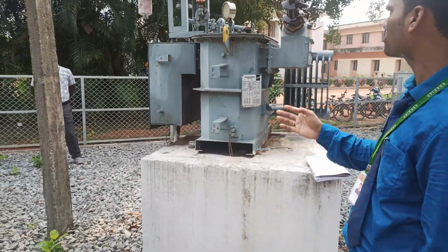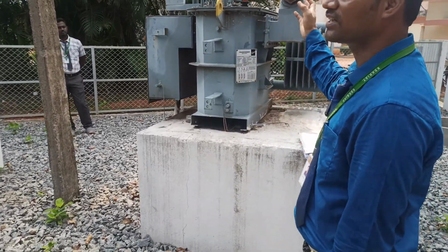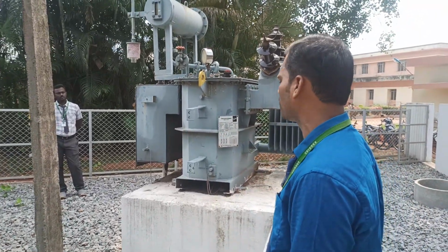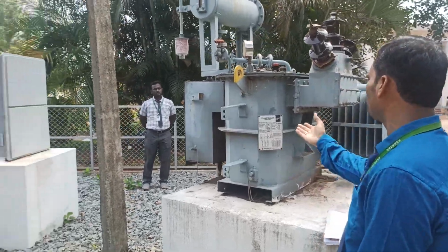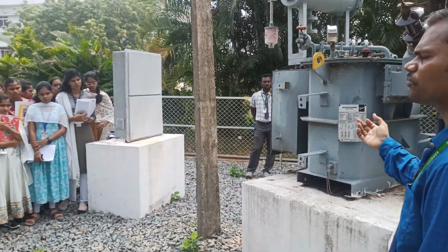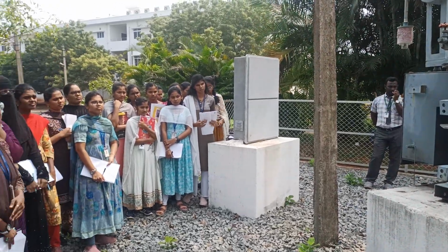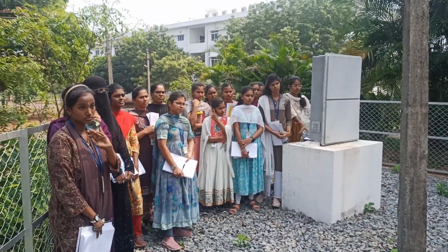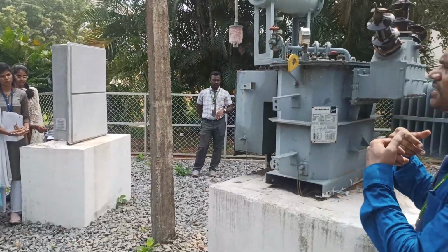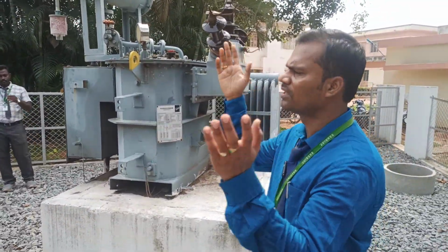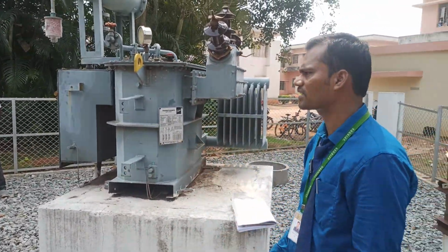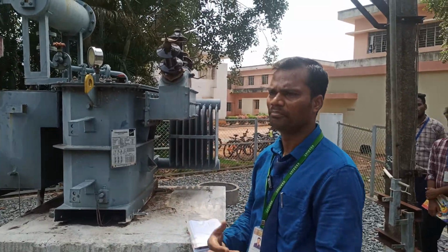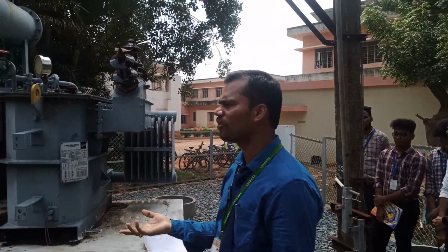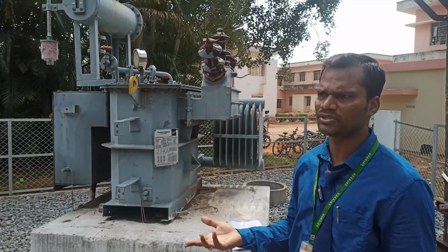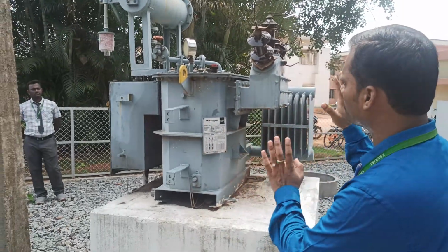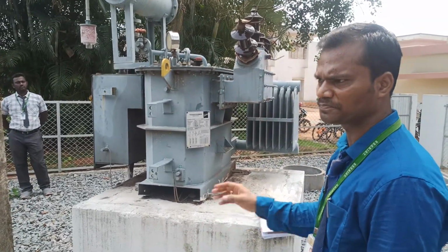When you do the product, automatically we can find out the rating of the transformer. Transformer rating will be in terms of what? kVA. So you can see if you multiply both, the rating of this transformer is 160 kVA, the product of voltage and current. Here power factor we are not going to take into account. Why? We don't know what kind of load we are going to connect. For example, sometimes they may connect inductive load, sometimes resistive load, sometimes capacitive load. Based upon the load, it may be resistive, inductive or capacitive. That is why the load is not known. The transformer manufacturer will specify only what? kVA, okay.